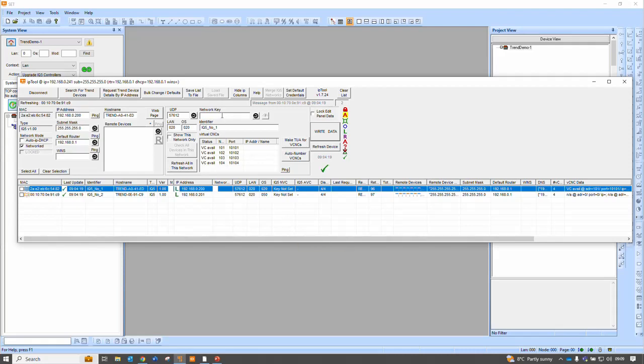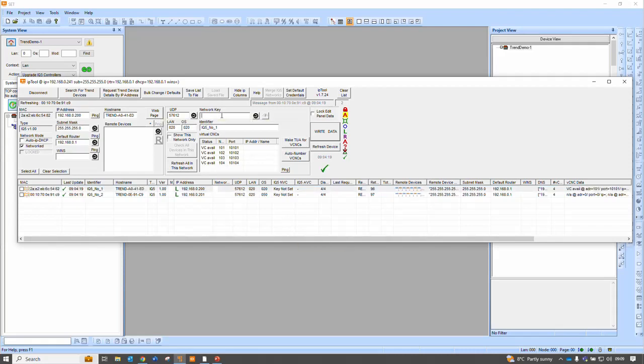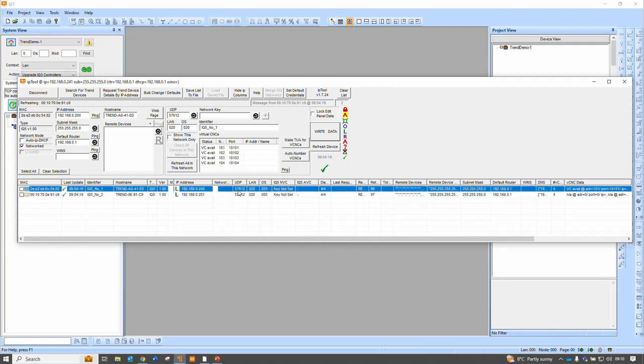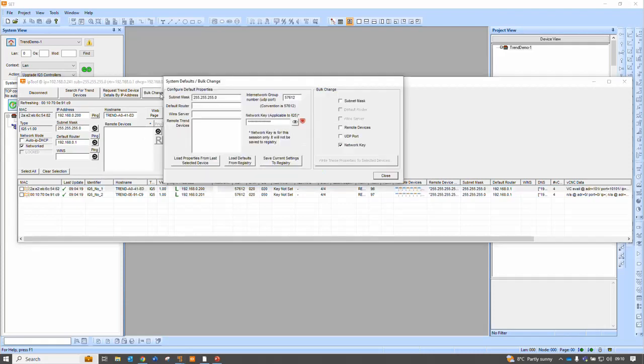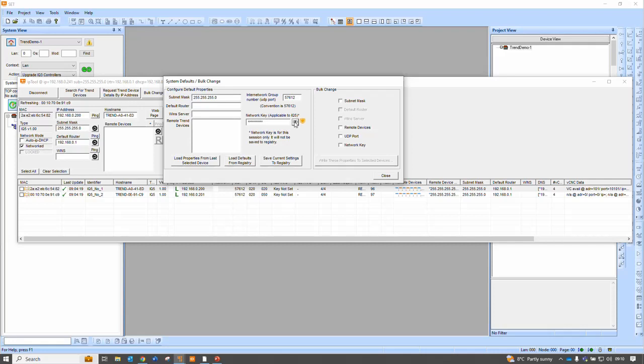Now, if I go to my controllers, I need to type in one critical piece of information here, and that is the network key. That needs to be the same for every controller I wish to join this network. So for me, it's only two controllers. It could be a thousand. Now, I could go ahead and type these manually into this box, but that leaves me slightly open to mistyping human error, which I'm very susceptible to. So we won't do that. What I'm going to do is type in my network key here. Now, I've misspelled that quite clearly, but just to prove it doesn't really matter. I'm going to do it as a bulk change. In fact, that's going to bug me, so I am going to change it to something more sensible. Better.